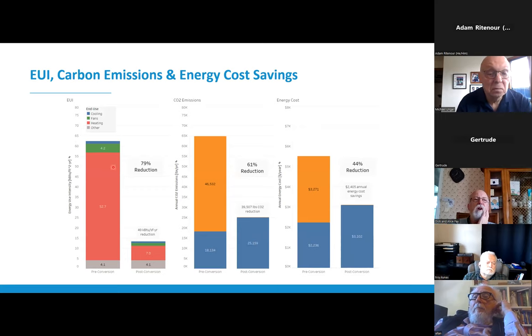So we did say that we reduced our total building energy use by 79%. What does that mean? Oh no, this is total building energy reduction of 79%. So what does that mean if we were to look at that with other metrics? Because sometimes it's not the EUI that you're looking for. Sometimes it's carbon emissions. Sometimes it's energy costs. So in terms of CO2 emissions, we reduced our CO2 emissions by 61%. And as far as energy costs go, we did reduce our energy costs by 44% by switching to a VRF DOAS system.